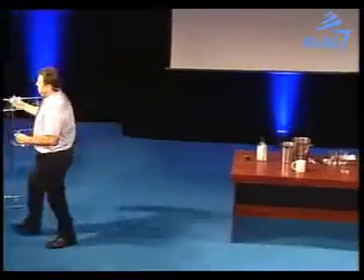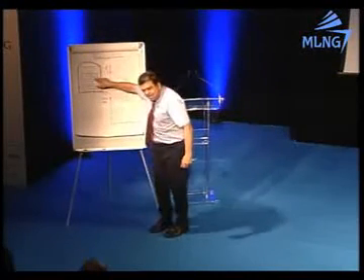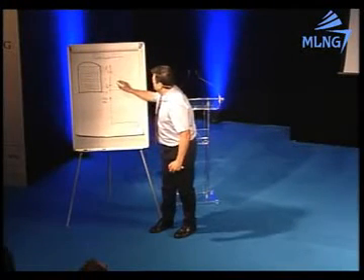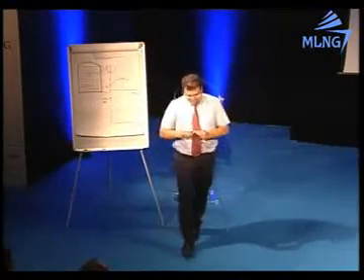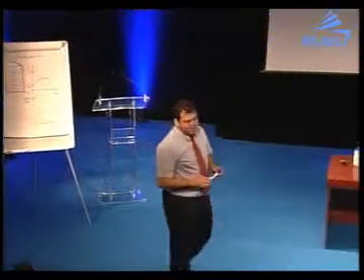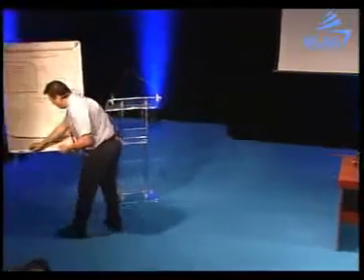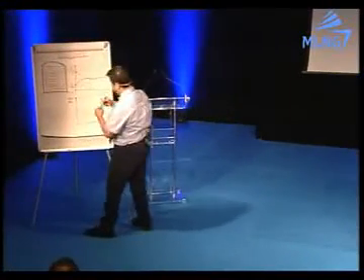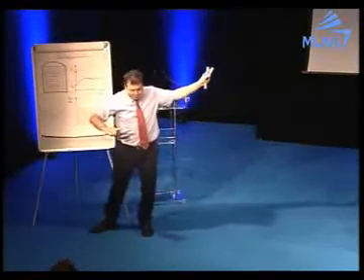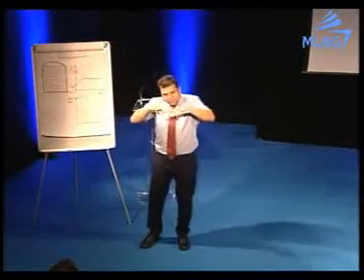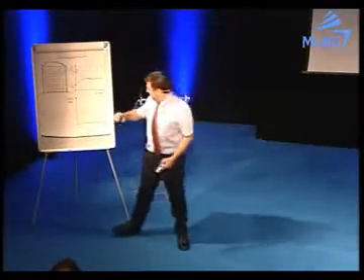As we mentioned before, the preferential boiling is methane. So the remaining liquid's density is heavier and heavier with time. And then, when the density equalizes, remember the cup of coffee? If we break the surface, then immediately and explosively it boils.